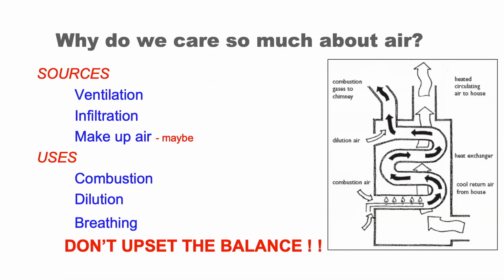So we talked a lot about air. Why do we care so much about it? The illustration on the right is a lower efficiency furnace, which is requiring several types of air. It has, of course, distribution air that's moving around the heat exchanger chamber. That would be this white arrow that's moving through here. The combustion air, which is moving in, merges with the fuel and moves up through the heat exchanger, and dilution air, and then taking it out the vent system. So you need to know what the sources are for your air and what they're being used for, and you don't want to upset the balance.